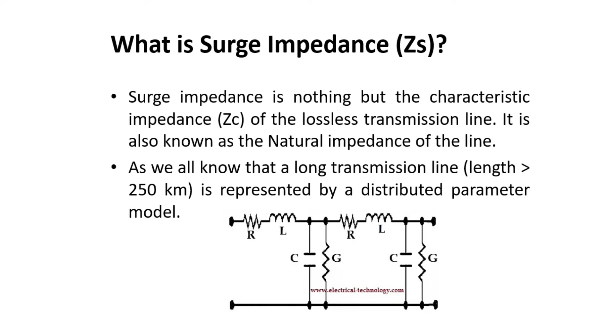What happens is that when different values of the load are connected, at some point we have a capacitive behavior and at some point an inductive behavior. When the line is charged, the capacitive component feeds reactive power to the line while the inductive component absorbs the reactive power. If we take the balance of the two reactive powers, we arrive at the equation that the reactive power absorbed by the inductive component is equal to the reactive power fed by the capacitive component. Then this equation becomes balanced.